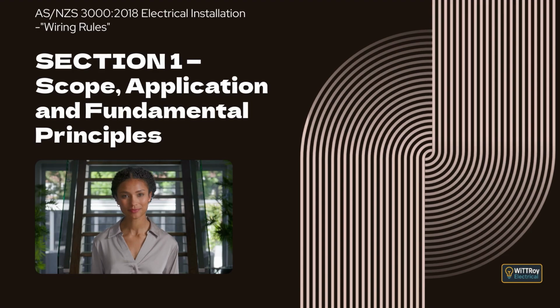Clause 1.4.66 is functional earthing, often shortened to FE. This is an earthing arrangement provided to ensure correct operation of electrical equipment, or to allow reliable and proper functioning of electrical installations. Clean or low-noise earths used for electrical equipment may also be considered functional earthing. Clause 1.4.67 is functional unit. This is a part of a switchboard assembly that includes all the electrical and mechanical elements needed to perform one complete function. Conductors connected externally, such as auxiliary cables, are not considered part of the functional unit.